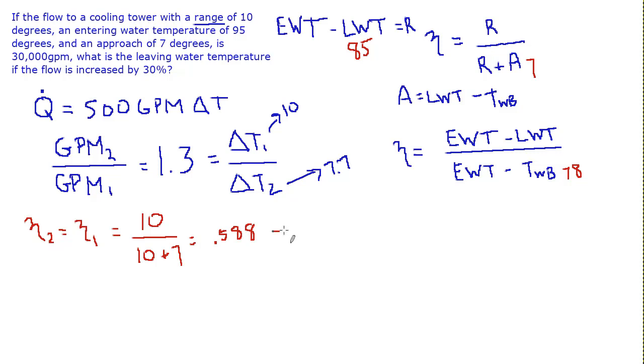Now applying that for efficiency 2, we know the new range is 7.7. And the denominator then is 7.7 plus the new approach. Let's call it A2, and we can solve for that. I trust you can do the algebra. You'll discover that A2 equals 5.4.